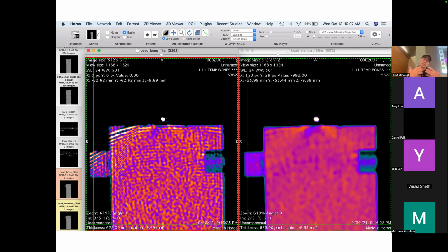Given the high frequencies that we can display and reconstruct on here, those artifacts come through because we can actually see things at this frequency. And they're usually caused by a very sharp edge just missing the edge of a single detector, or transiting two detectors, as you move your angles, and it causes these spray artifacts.